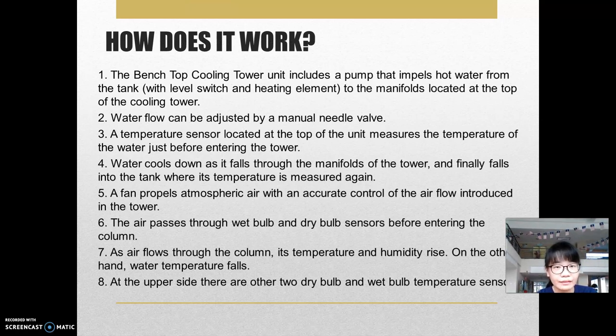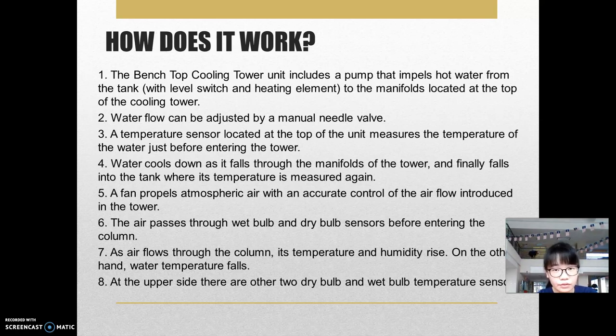Now we move on to how the bench cooling tower works. The bench cooling tower uses a pump that pumps hot water from the tank up to the manifold at the top of the cooling tower. The water flow rate can be adjusted manually. A temperature sensor located at the top of the unit measures the temperature of the water entering the tower. The water falls down as it flows through the manifold of the tower and finally pools into the tank, where its temperature is measured again. A sensor also measures the air as it enters in front of the tower.